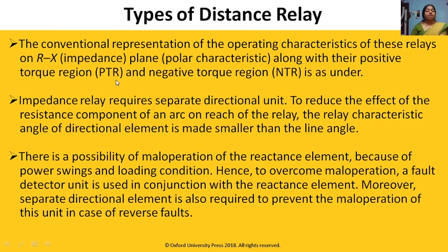Types of distance relay. The conventional representation of the operating characteristics of these relays on the RX plane, the impedance plane, and polar characteristics, along with their positive torque region and negative torque region, is shown in the next slide. Impedance relay requires a separate directional unit. As we have seen, the impedance relay is a non-directional relay, so it requires a separate directional unit.